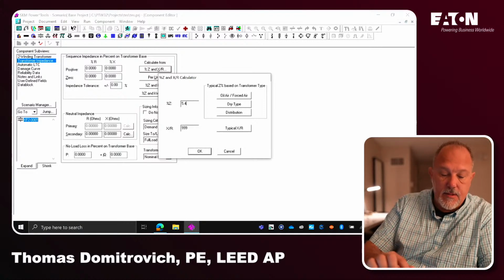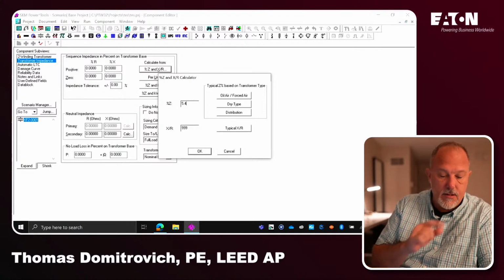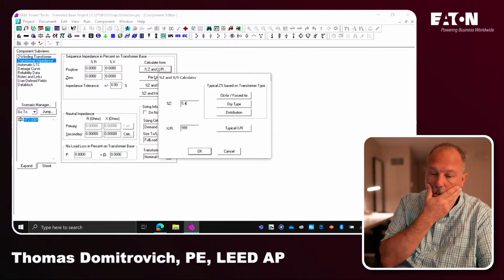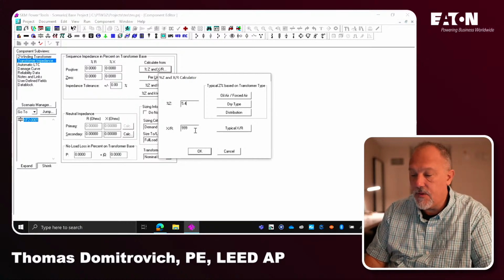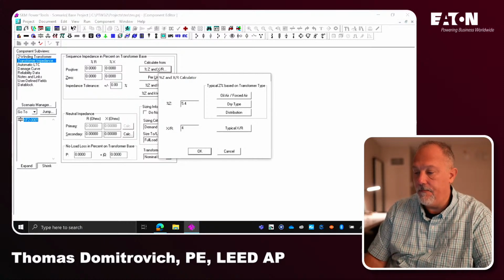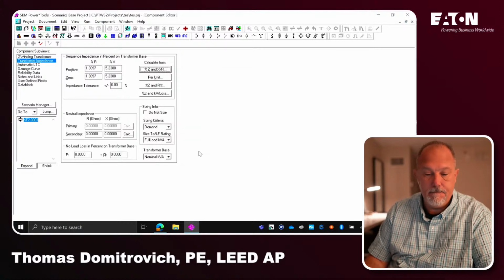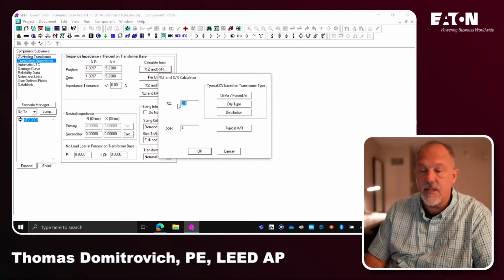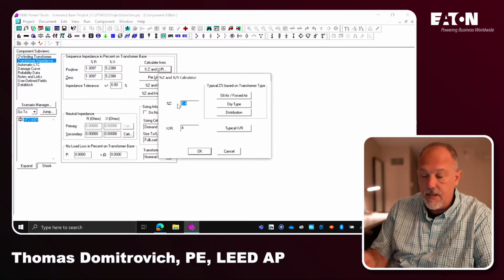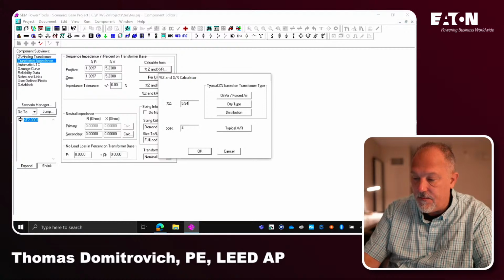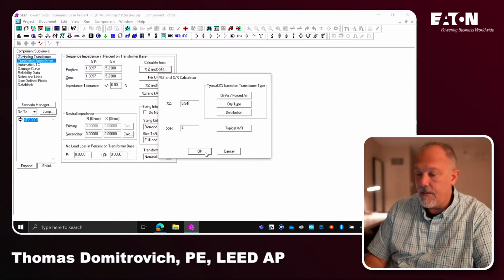And I've got to look and see what the X to R ratio was. Did we put an X to R in for the transformer? Source, conductor 1, transformer 1, we said the X to R ratio was 4. So I'm going to put 4 and hit OK. And actually, I'm going to go back to this, and we said it was 5.4 plus 10%, so it was 5.94. There we go. Dry type.